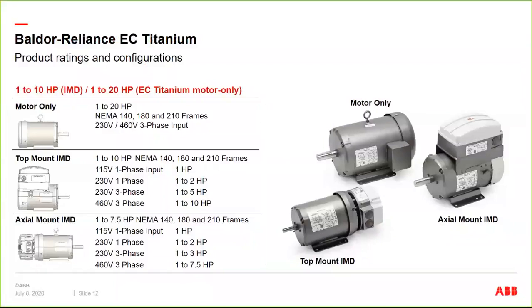And then when you're looking at it from an integrated motor and drive standpoint, you can get it in a top mount unit up to 10 horse, or in the axial mount up to 7.5 horse, and that's just a frame limitation. So on the axial mount, we go up to a 180 frame with a rear mount drive on it, which gets us to 7.5. In the top mount, we can go up to a 210 frame, and that'll get us up to 10 horsepower.